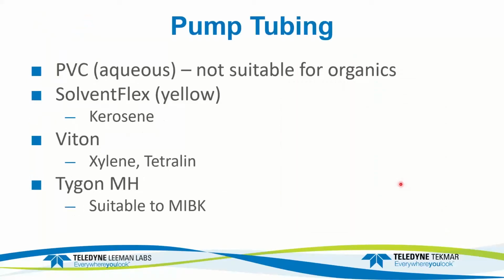And then finally, the pump tubing. Typically, you replace the pump tubing. The PVC that's used for aqueous is not suitable. The kerosene will cause it to swell up and it won't pump. So we use Solvent Flex, which is the tubing that has the yellow coloring to it. That works for kerosene very, very well. For some other organic solvents, there are other types of pump tubing materials available if you wish to use those. Okay.